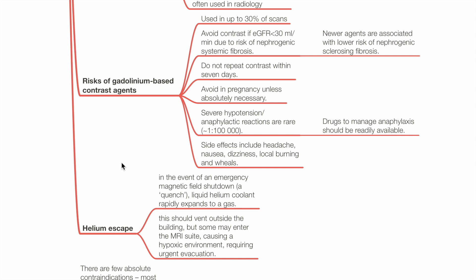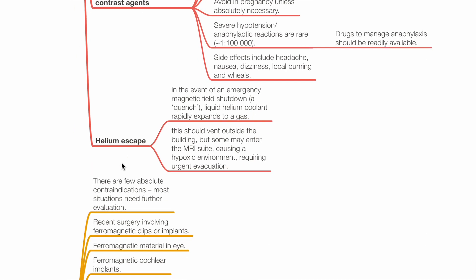Side effects of gadolinium include headache, nausea, dizziness, local burning, and wheals. Helium escape: in the event of an emergency magnetic field shutdown, liquid helium coolant rapidly expands into a gas. This should vent outside the building, but some may enter the MRI suite, causing a hypoxic environment requiring urgent evacuation.